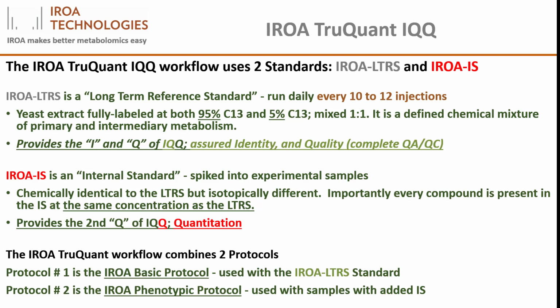The LTRS provides a complete QA/QC for instrument performance. As a defined but chemically complex isotopic material, when the instrument falters in the middle of a run, you will see this change, as well as a method to correct, if possible. To be most effective, there should be multiple injections of the IROA-LTRS over the duration of the analysis, for instance, at the start and end of the run and approximately every 10th injection during the run.